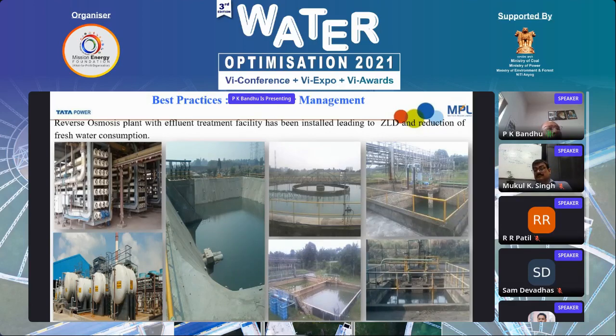So there is a 100% balance in the wastewater, and we are not draining any water. You can see there are buffer pits, so that no process water goes outside the plant. It is collected in this system and recycled through this RO, and what is not required through RO is directly used after treatment in the service water system. We have the clarifier system for ash water recovery, which goes to the ash pond occasionally.